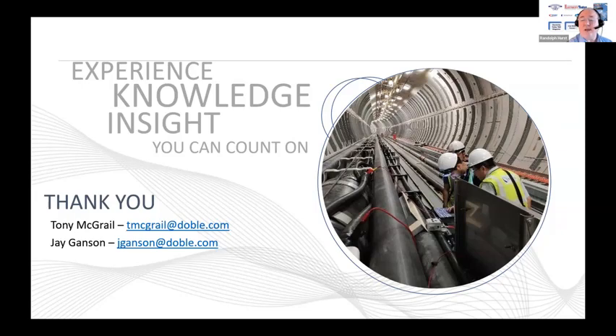Okay, so here's a question. What DGA gases and levels are a cause for concern in cables? You can do this similarly with bushings. At the start, you test it and you would assume that there are virtually no dissolved gases in there. So the appearance of dissolved gases implies that you've got some problem which has generated over time. You will get some breakdown at lower temperatures of the oil, possibly of the paper, in an oil-filled cable, but you've then got to take that as a slow degradation. What you're looking for is a sudden rise in any of the key gases that you'd expect in a transformer, much as Chris talked about before.